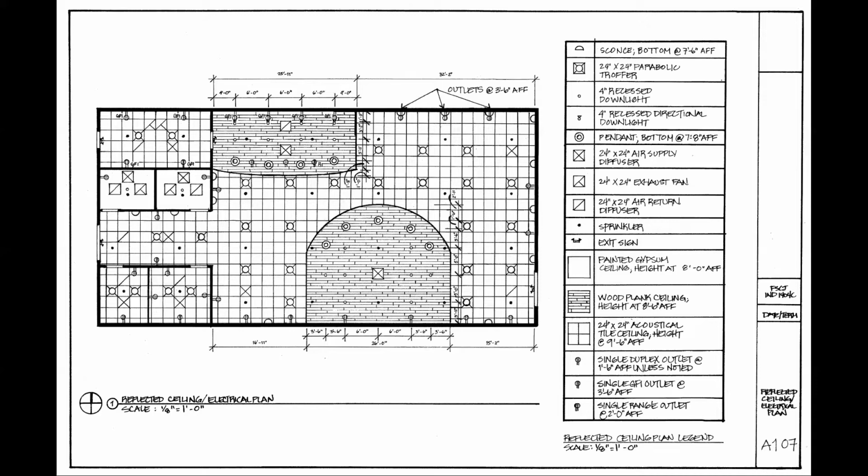But as a general rule, you try to place them sort of far away, up against the edges of the room a little bit, so that you don't have cold air blowing straight down on people. But they also are sort of far away from the thing that we're going to look at next, which is the air return diffuser.